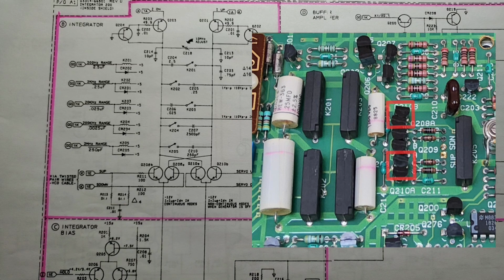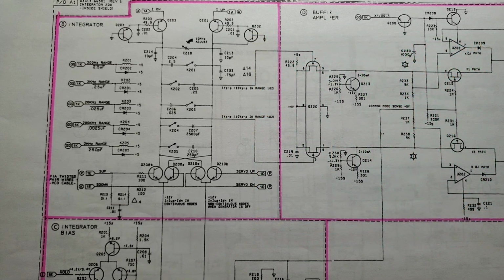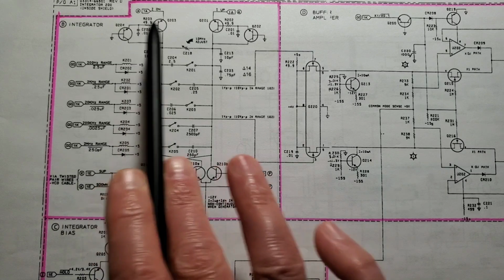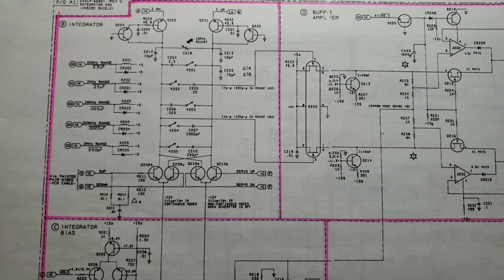Also, instead of one, there are 2 differential pairs of transistors. This pair here is only active when operating in non-continuous mode, like the arbitrary mode. These base signals labeled as servo up and down that was mentioned come from a separate control and timing circuit that can hold each of these transistors in either up or down state, and that's in concert with the DAC chip when initiating a new vector with I up and I down generating a ramp. When in continuous mode, this pair of transistors are active instead, which we've already talked about, where these trigger signals S up and S down are fed in from that hysteresis comparator. So we might as well have a quick glance at that now.